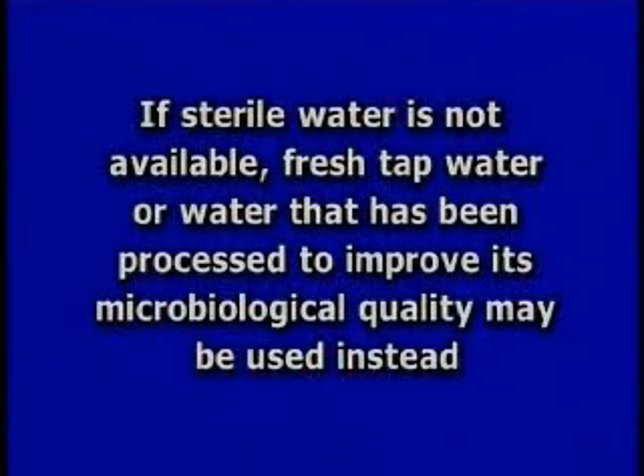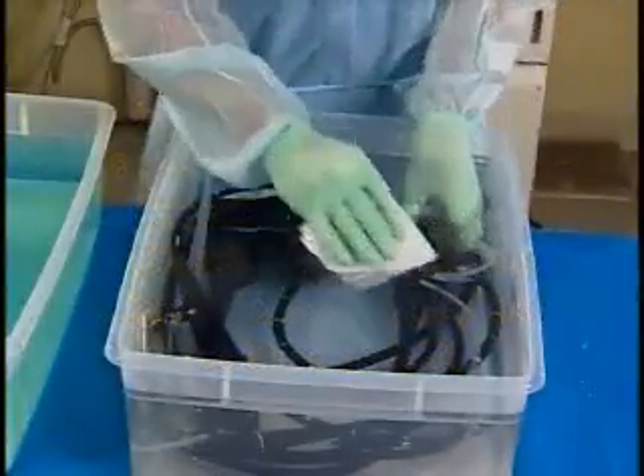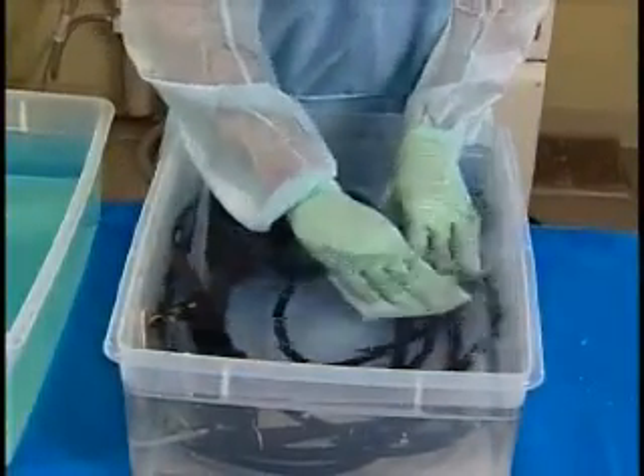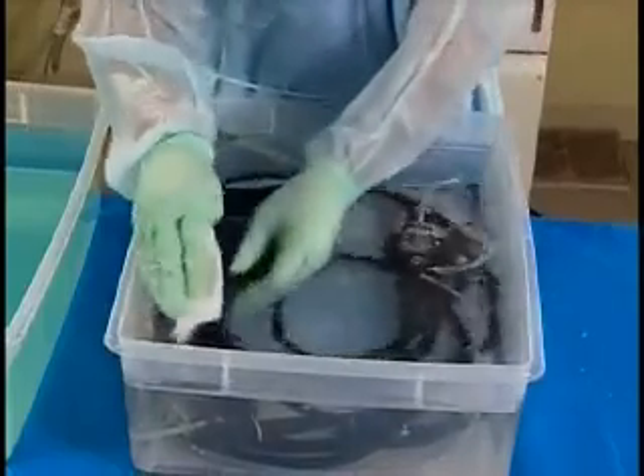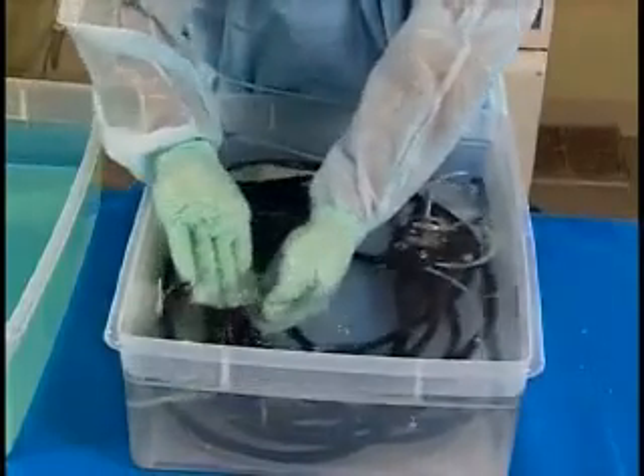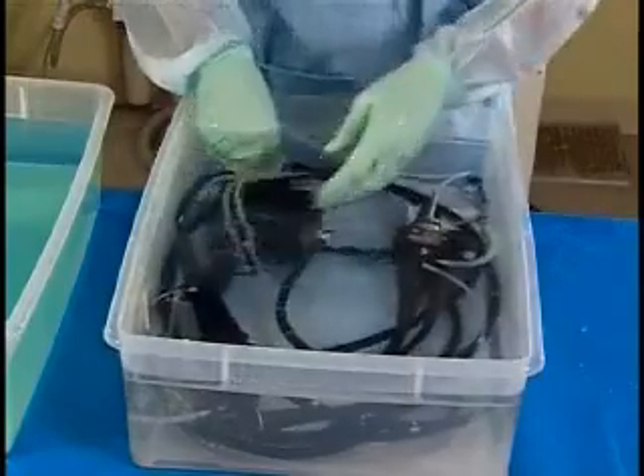If sterile water is not available, fresh tap water or water that has been processed or filtered to improve its microbiological quality may be used instead. However, always consult with the infection control representative within your facility on the hospital's policy regarding water quality. With the instrument submerged, use a fresh, sterile, lint-free cloth to thoroughly wipe and rinse all external surfaces.